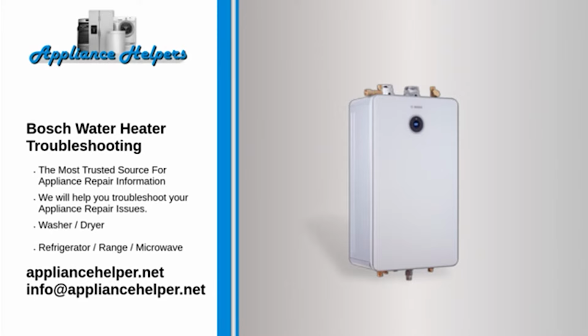The water is not hot enough. Check the selected temperature if it's not too low. Adjust this to a higher setting and see if it solves the problem. Clean the inlet filter screen as this can increase flow through the heater. Check to see if the water path has any obstructions. Make sure that all shower heads, faucet aerators, and whole house filters are clear of debris. Verify that the gas type of the heater is similar to the gas that is being supplied.